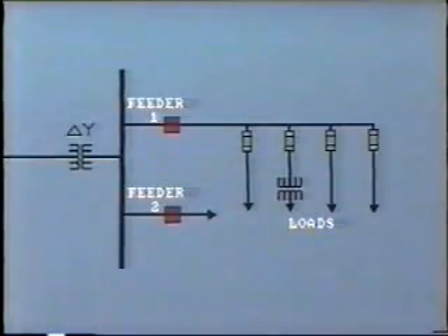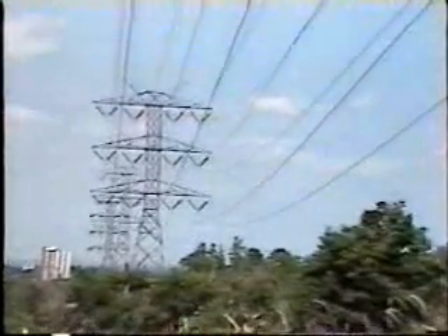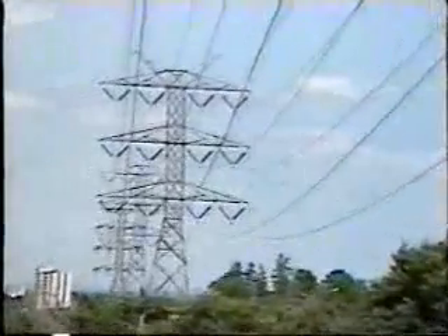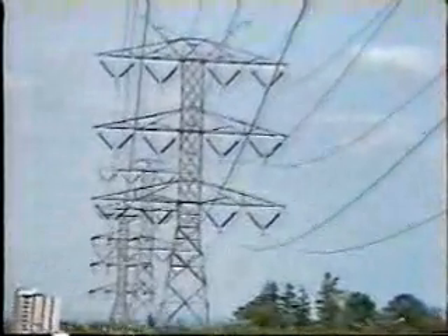Now, bearing in mind all that we have said, it is obvious that the type of protective scheme chosen will depend very much upon the installation itself. For example, it is certainly far more simple to protect a single radial distribution line than a transmission line which forms part of a complex network. Moreover, the isolation and outage of a transmission line may cause interruption of power to many, many more customers than the outage of a single distribution line.